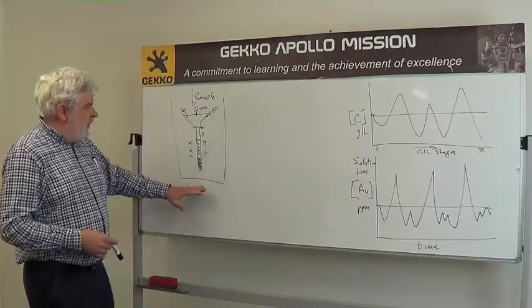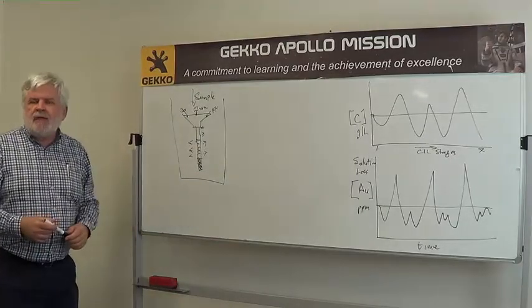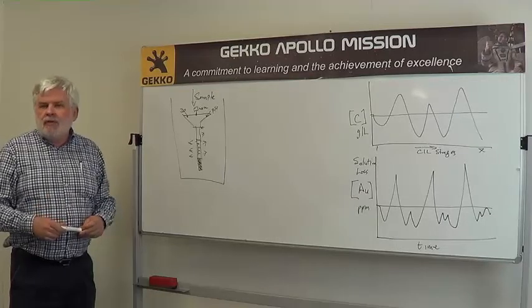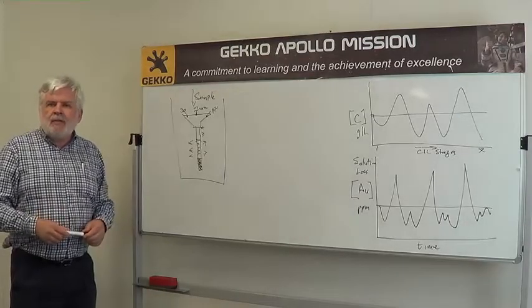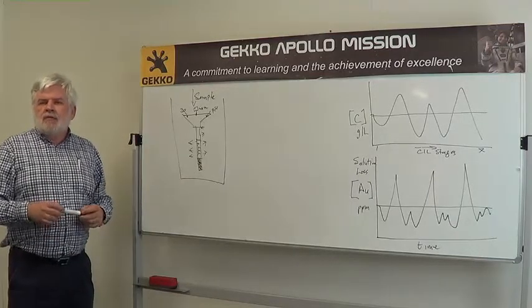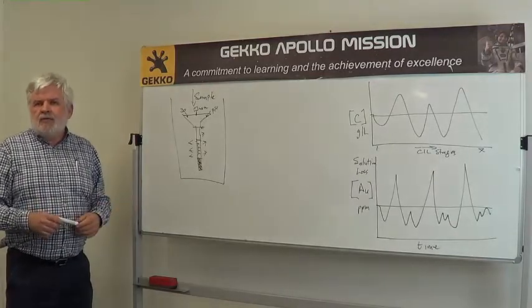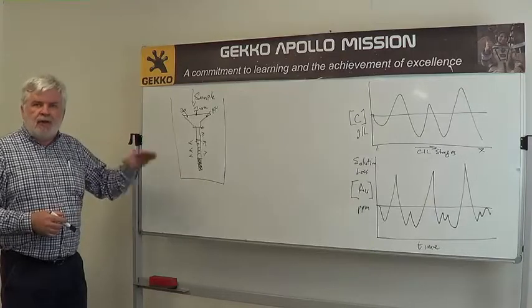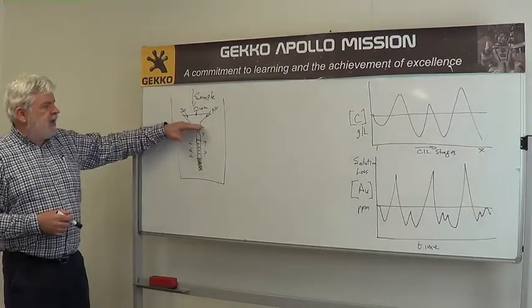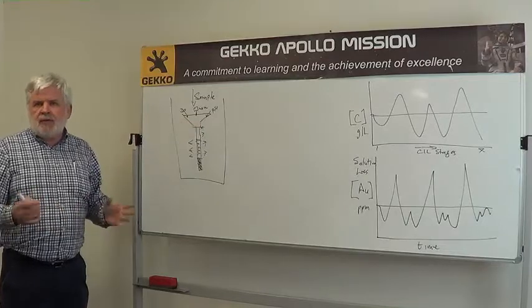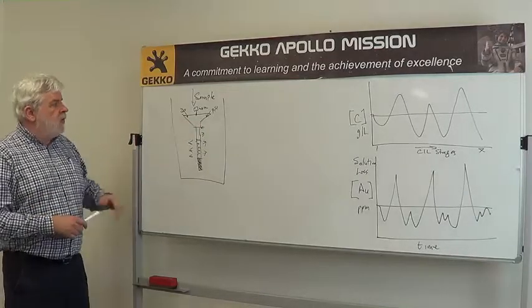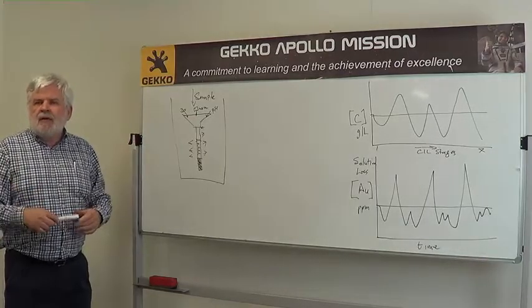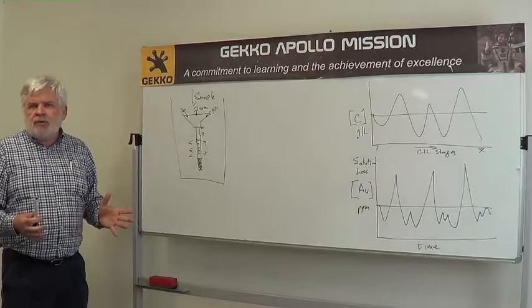Here is a very simple diagram of the instrument we developed. What it's actually doing is mimicking what operators do manually — take a sample of the carbon, measure its volume, and convert that to a grams per liter figure. We have this instrument at ground level, not up on the tanks. We have a sample cone of about 20 liters, which is a much bigger sample than taken manually, and we fill that cone from a given tank by siphoning the sample through a plastic pipe from the tank surface, so no pumps are involved.